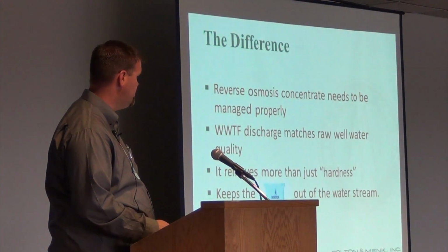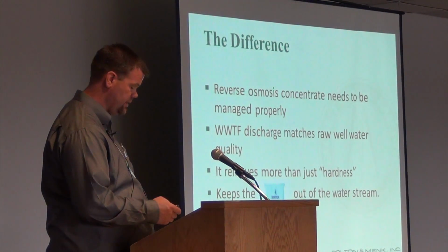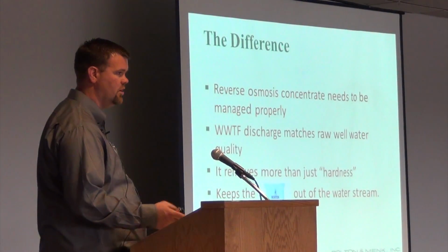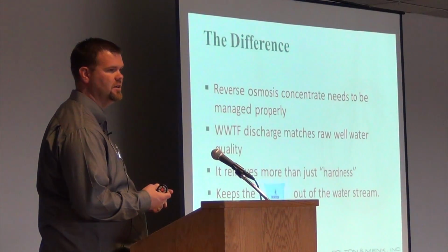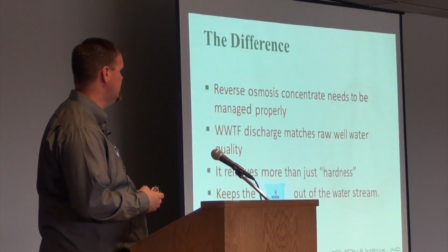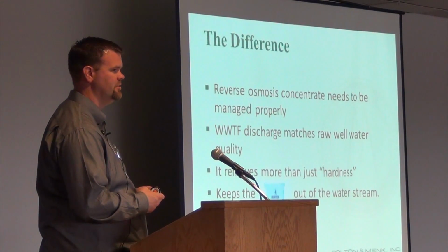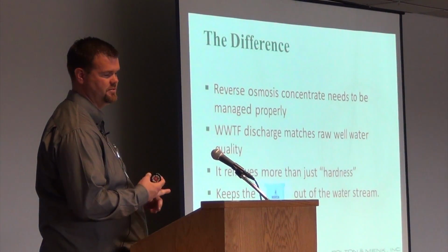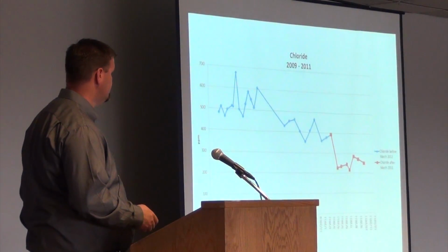Wastewater treatment plant basically matches the well water quality. The one thing about our RO, and this is a number of clients, St. Peter being one, Redwood Falls, it removes more than just hardness. So there's other ways to do this, lime softening, EDR process. There's other ways to soften water, take this out. The benefit for a lot of communities is this removes more than just hardness. It takes out the other dissolved solids too, and secondary standards of dissolved solids, sulfates in drinking water. And it ultimately keeps that water out of it.